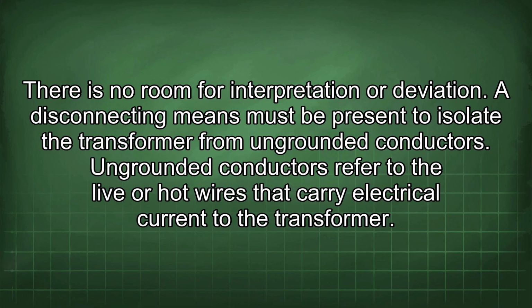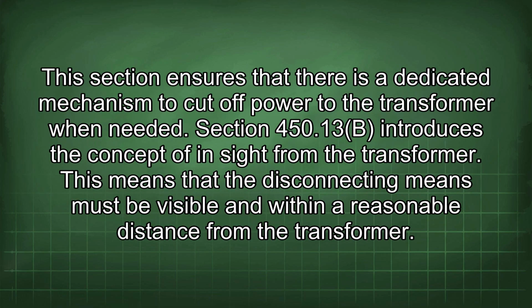A disconnecting means must be present to isolate the transformer from ungrounded conductors. Ungrounded conductors refer to the live or hot wires that carry electrical current to the transformer. This section ensures that there is a dedicated mechanism to cut off power to the transformer when needed.